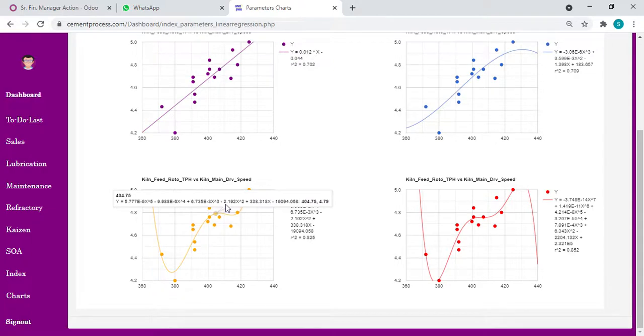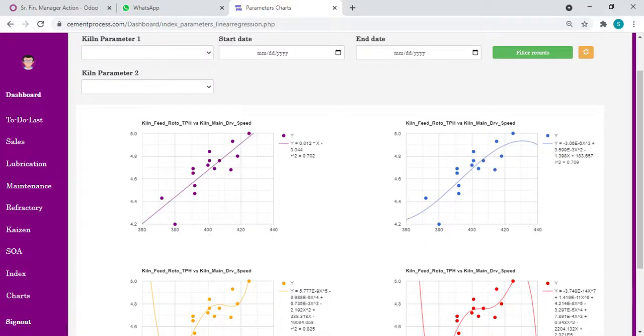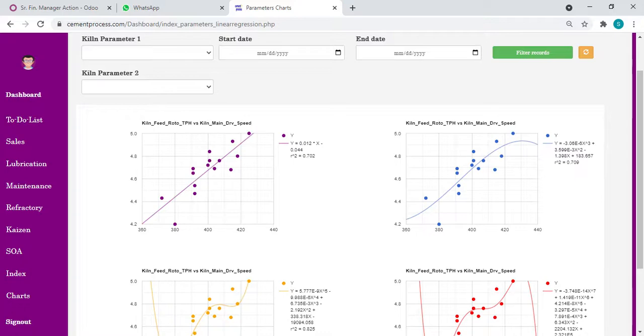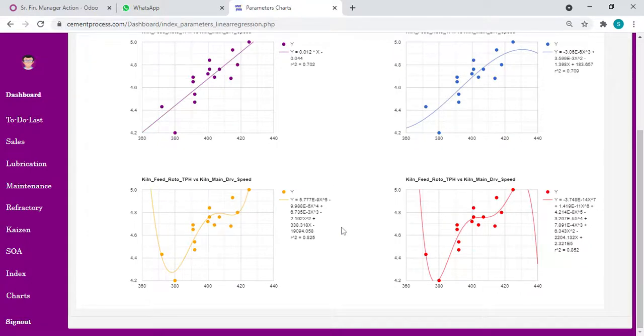From this, mostly in our industrial cases, we can take linear correlations or go up to polynomial second degree. We can have some idea what could be my kiln RPM at 400 feed, at 420 feed. This is all data we are not taking from some outside formulas. We are interpreting our data from our live records. This is not in the books, it's not a standard formula. Whatever parameters we are running in our plant, it's interpolating the same data. Using this technique, we can compare granulometries in raw mill, in cement mill, particle size distribution, any graphs.